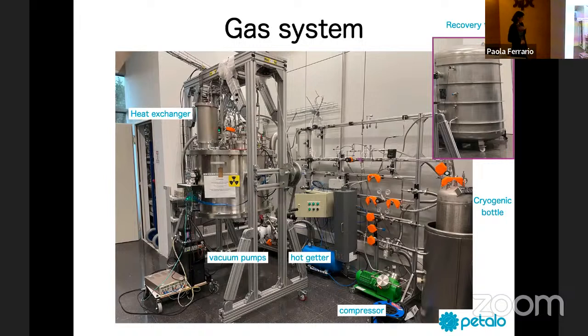So the cube is inside the vacuum vessel. We use a heat exchanger, which basically puts into contact the gas that enters the cube, which is at normal temperature, and the gas that exits the cube, which is already cold. So by this transfer, you can optimize your cooling and use less power. And well, finally, I wanted to mention the recovery tank, which is much bigger than that. I just had to put the insert here.